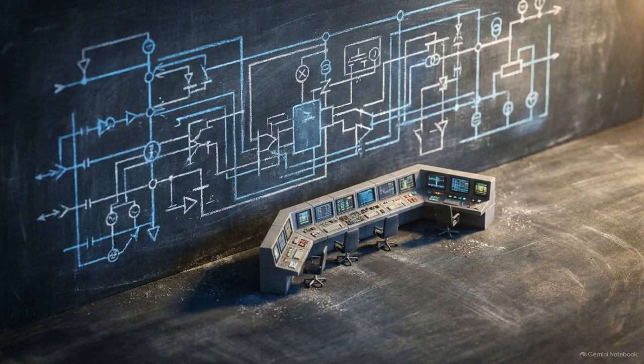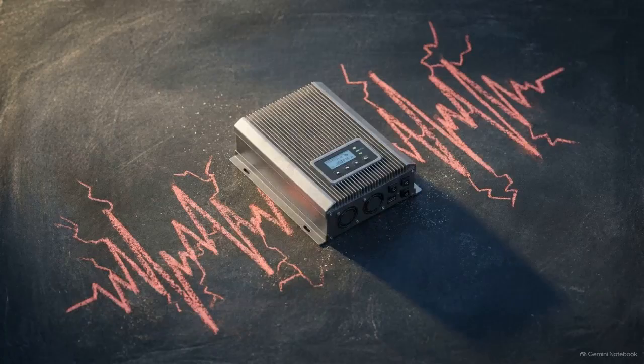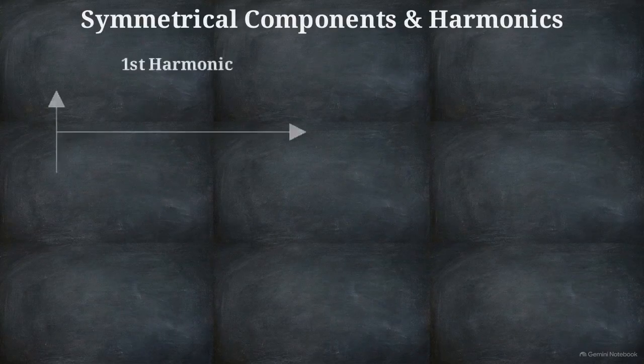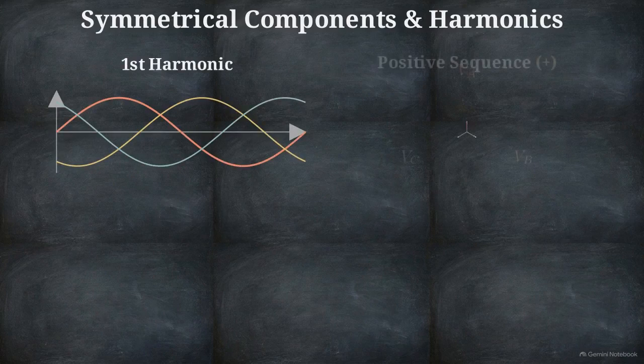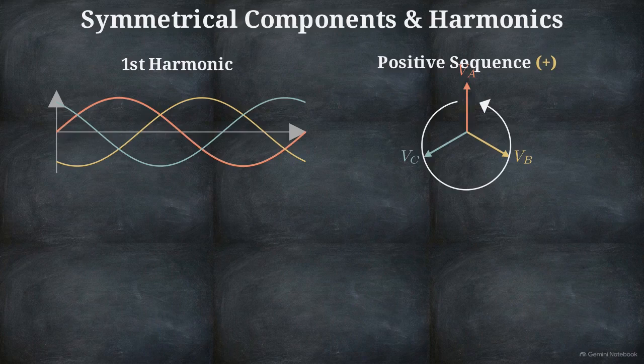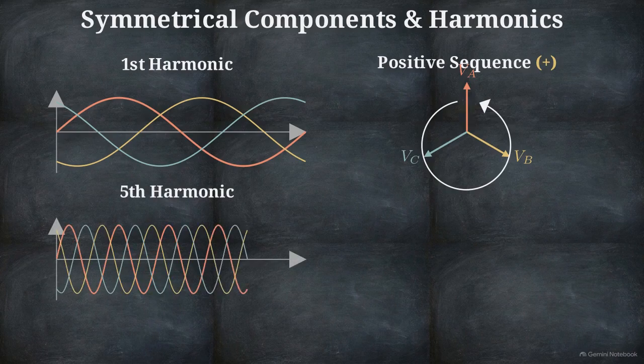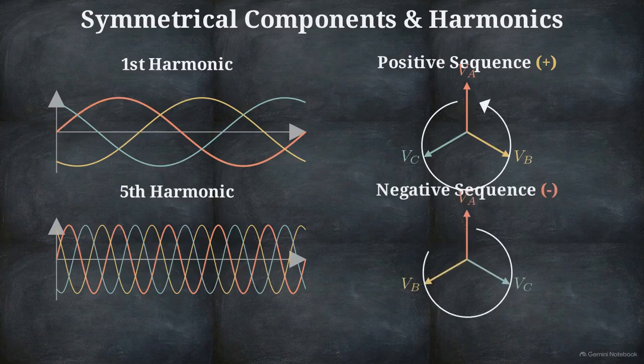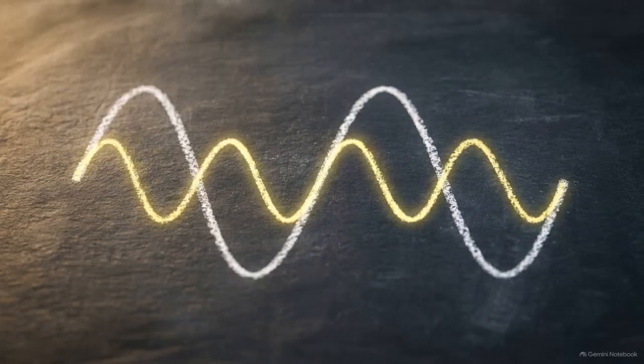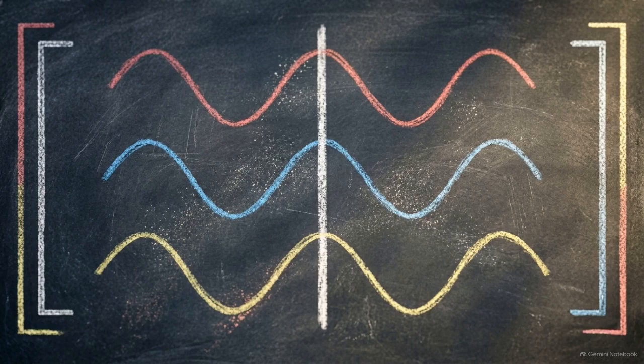Today, grid operators face issues beyond steady-state faults. Modern power electronics, like inverters and variable speed drives, introduce non-sinusoidal waveforms and severe harmonic distortion. Fortescue's method applies here too. We can map specific harmonic frequencies to their inherent rotational sequences. The baseline first harmonic rotates in the positive sequence. The 5th harmonic, however, inherently rotates in the negative sequence. Triplen harmonics, multiples of 3, like the third or ninth, are inherently zero sequence. By definition, their wave peaks align perfectly across all 3 conductors at the exact same time.